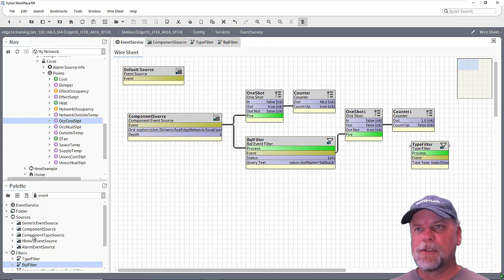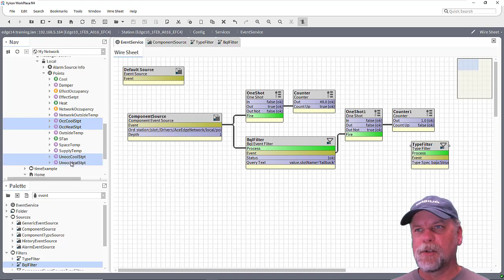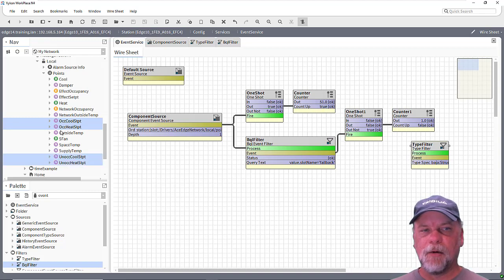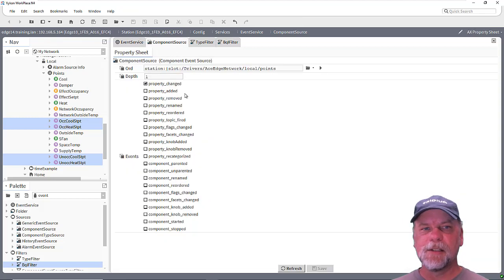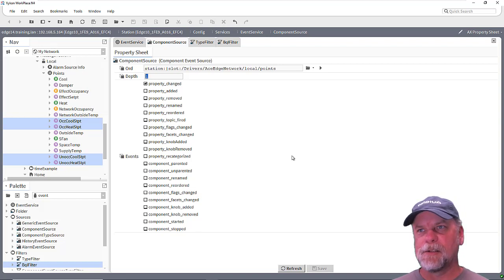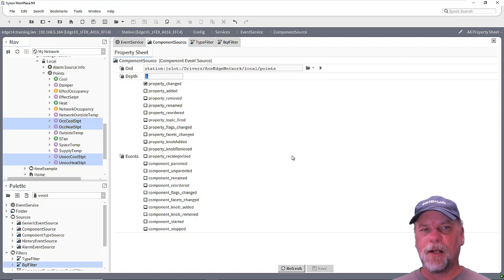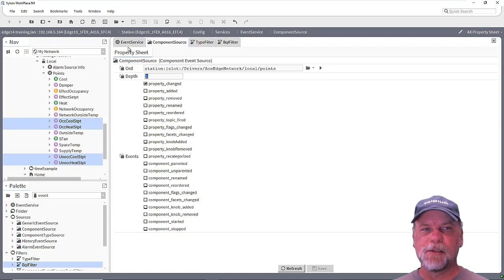Now we also have some different ways to go about it. Let's say for example I was really only concerned about these control points changing — and these happen to all be numeric writables, they're set points. So instead of maybe using the component source with a depth, one other thing to mention here is be careful about setting that depth. I wouldn't want to put this point at the drivers level and set the depth to 10 or something, where it's going to be subscribing to hundreds or thousands of components. You would probably have a lot of high CPU activity. So you want to be careful about how deep you set the subscription and how expansive the component tree is that you're subscribing to.